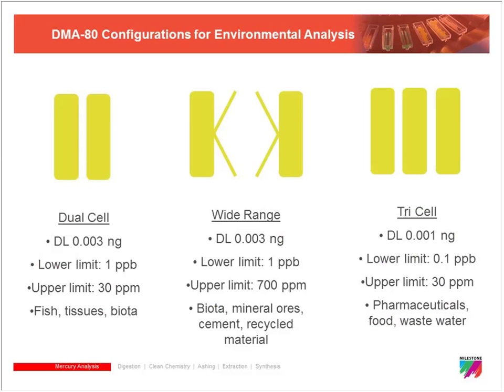We offer the DMA in 3 different configurations. What's going to be most common for your type of application, again, for biological fish and tissue samples, is the dual cell. It has a lower detection limit of 0.003 nanograms and an upper limit of 30 ppm. So it has a very dynamic range and is a very common configuration that we offer.